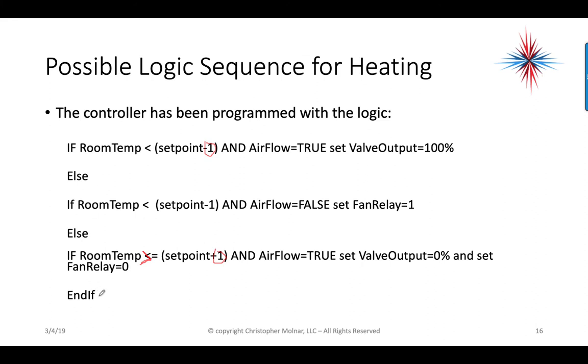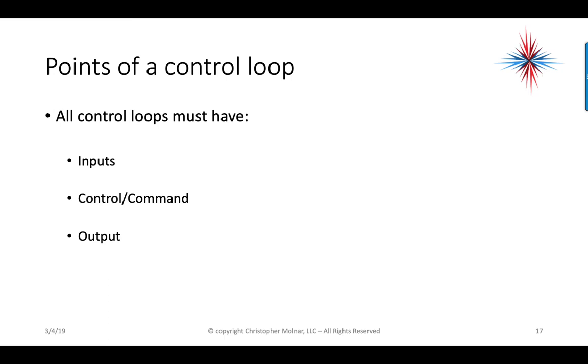Once this loop reaches the end, it goes right back to the start. We turned our fan on, and within less than 30 seconds it will confirm the fan is on, then open the valve to 100%. It continues going through this loop until the room temperature has warmed up to the set point plus one. Then it comes back, closes the valve, and turns the fan relay off. I could do this in two statements to give the fan a little more time to get the residual heat off the coil, but this is a simplified version. All control loops have to have inputs, control and command, and output — and they also have to have some logic that's part of the control and command.